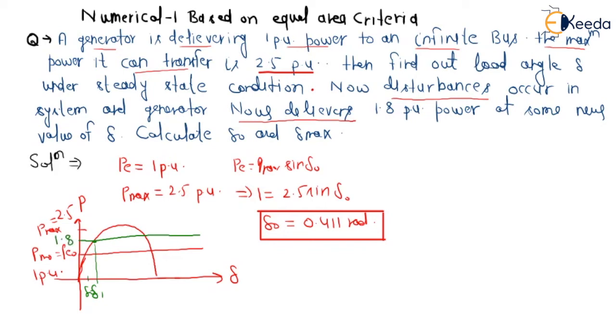We can see from the diagram the value of delta_max — up to what value it can go. If the generator is delivering 1.8 per unit power, delta_max will be the symmetrical point on the other side of the curve. Delta_max = pi minus delta_1. You can calculate this from the diagram.